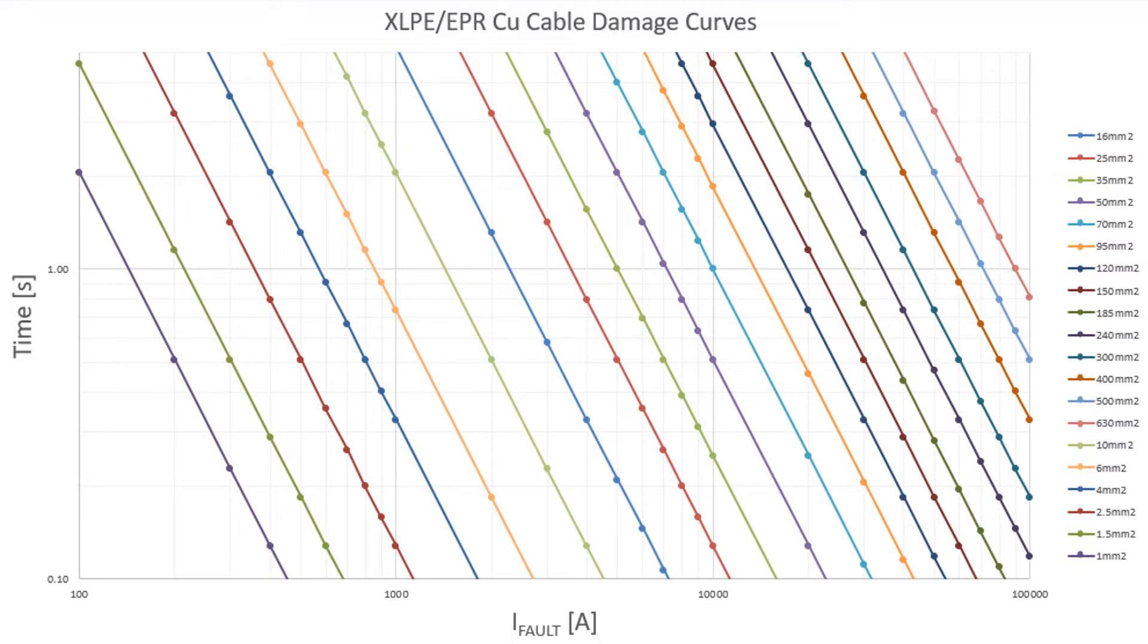Here we have a set of cable damage curves. Now how are these useful? Let's consider this green curve over here, which is the curve for a 10 millimeter squared cable. So let's say my fault current is 2000 amps. I come to the 2000 amp point on the horizontal axis, travel up to my curve, when I hit the curve I travel across to the time axis and I see I'm about 0.5 seconds. So a 10 millimeter squared cable can handle a 2000 amp fault current for about 0.5 seconds.